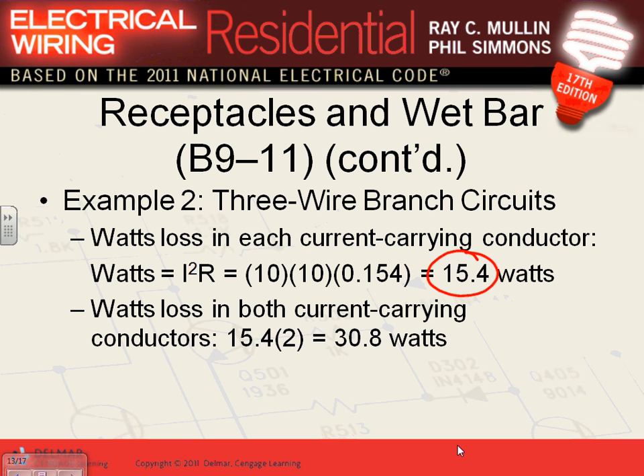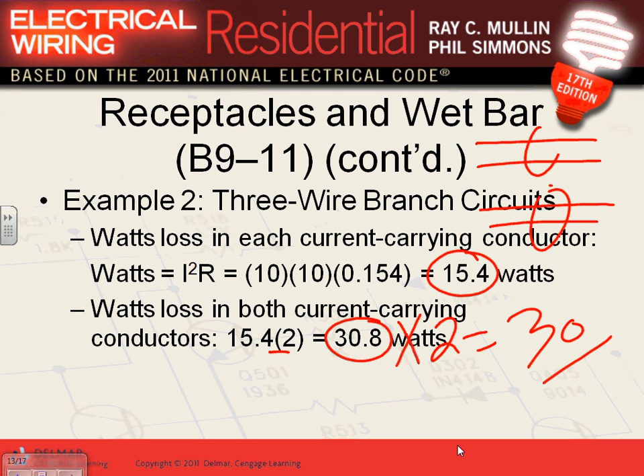If you run a multi-wire branch circuit like this, look what happened. The drop is 15 I squared R, and if you multiply it by 2, it's going to be 30. The first one, if it's not a multi-wire branch circuit, you have to multiply this by 2 again. That'll give you 30. So you cut the losses in the copper by half. Because remember, the first circuit has 2 wires, the second circuit has 2 wires. So this is only for 1 wire, so for 2 wires will be this. For 4 wires, because we have 2 circuits, it will give me 60.